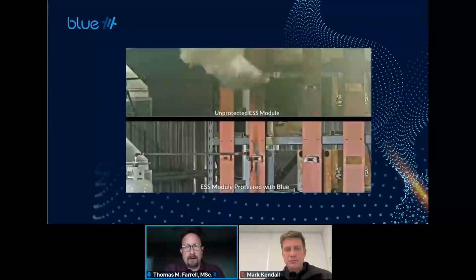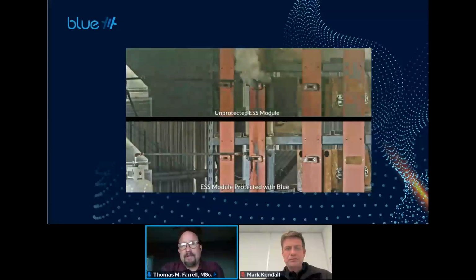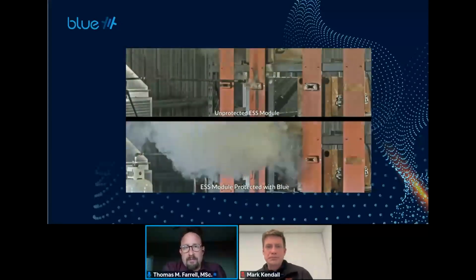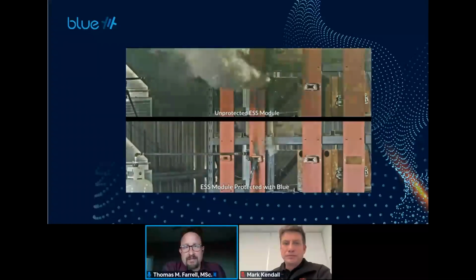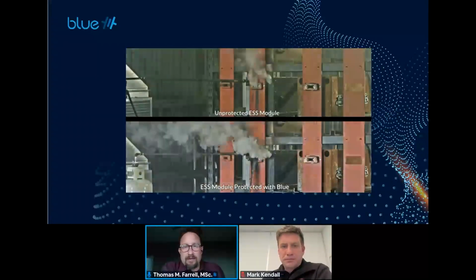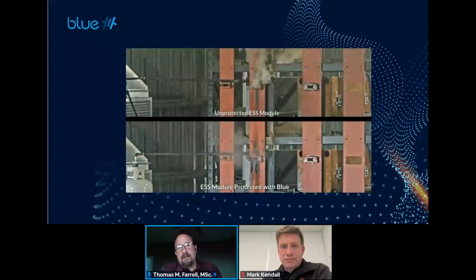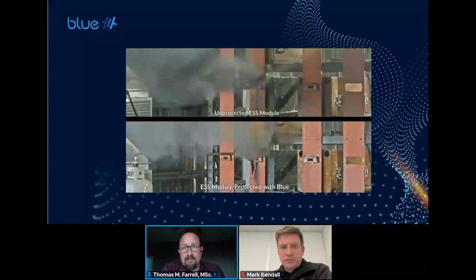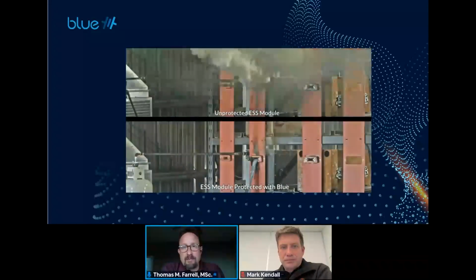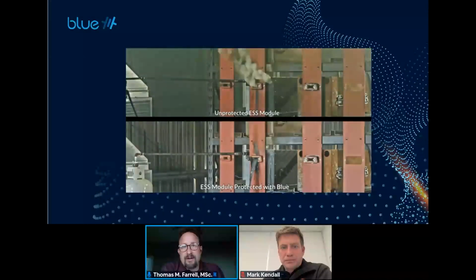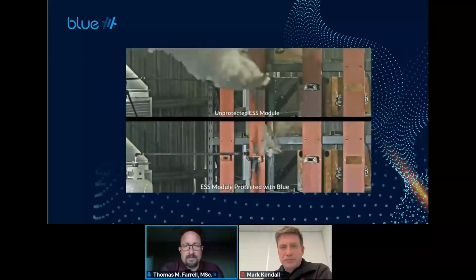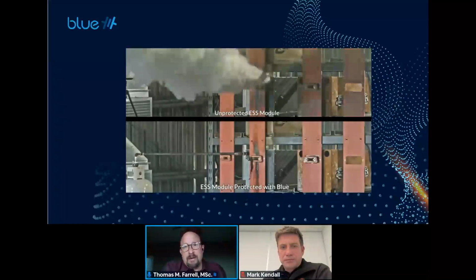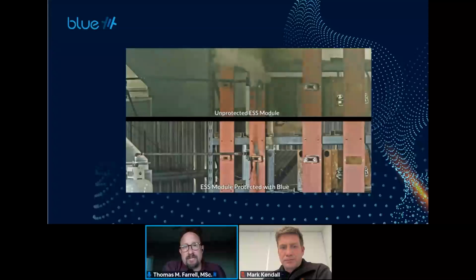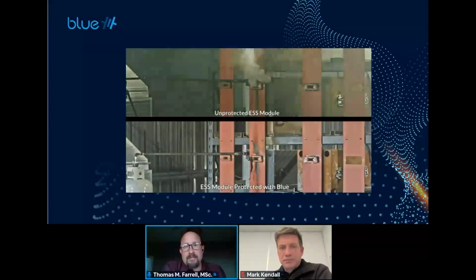So it's one thing to talk about these, but we should look at them. In this video, the top module is unprotected, and the bottom module has blue protecting it. Every time you see one of those chuffs of smoke, that's another one of those lithium-ion modules failing. The one with blue has a couple of short bursts, while the one on top just goes over and over. This is a loop that's been trimmed, but the top one was continuing to go for almost 40 minutes.